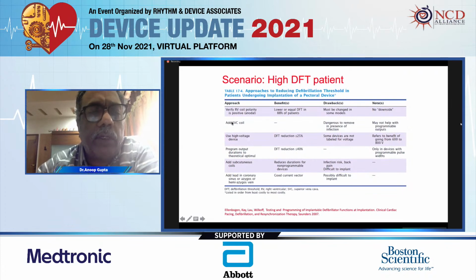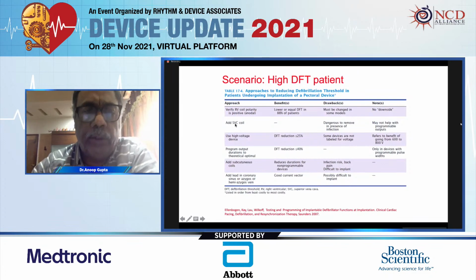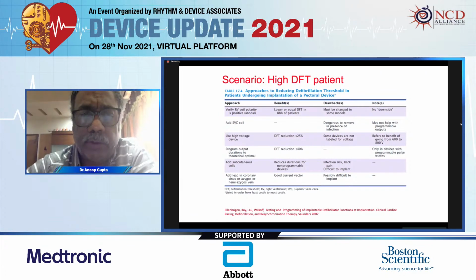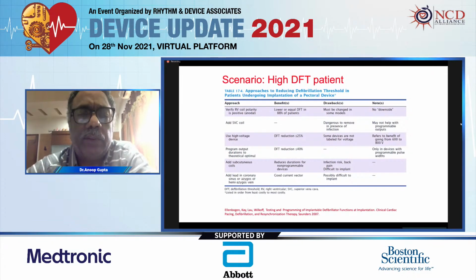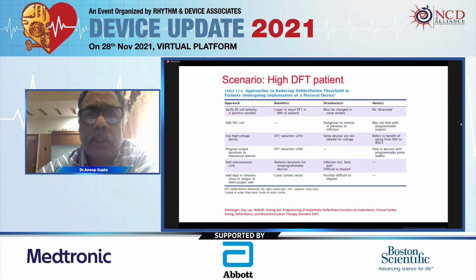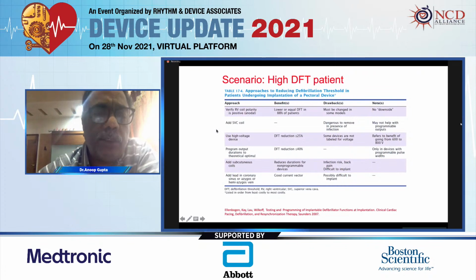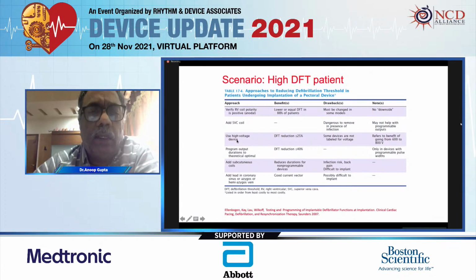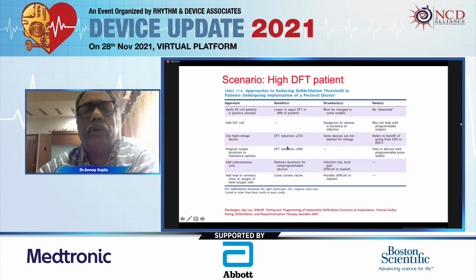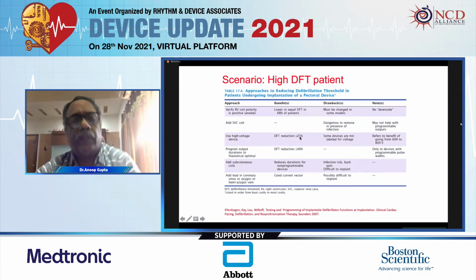Again, coming to single coil versus dual coil. Nowadays the preference is always single coil. We don't go for dual coil. The reason is that if the patient gets some kind of infection, or needs any upgradation, or there is some lead malfunction and you want to extract the lead, a single coil is much easier to remove. That is why, and in this patient we went for dual coil, because we knew it was a big heart and probably would require a dual coil. And that is what we call a cold can. If you have high voltage devices, you can reduce the DFT by 25%. Again, that's very, very important.